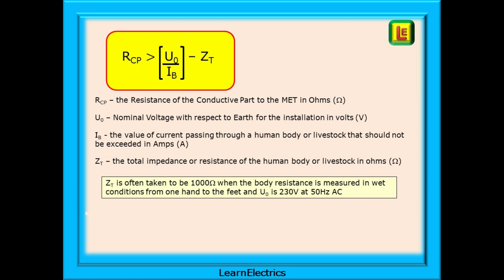Finally, ZT is the total impedance or resistance of the human body or livestock in Ohms. This information can be found in tables that list various situations, but in general, we take the figure to be 1,000 ohms, measured between a hand and the feet, in damp conditions.